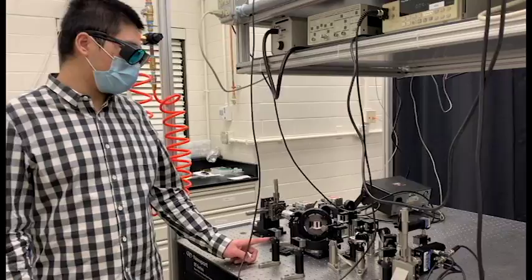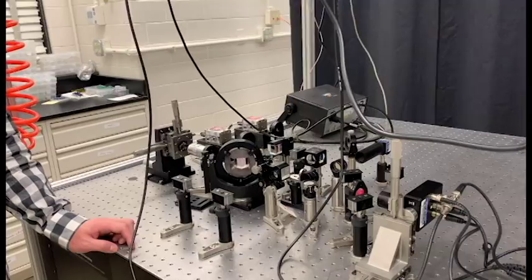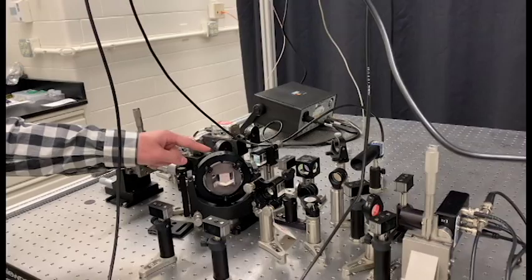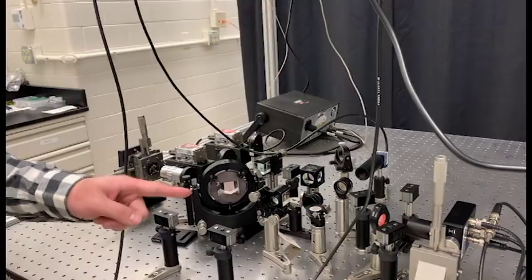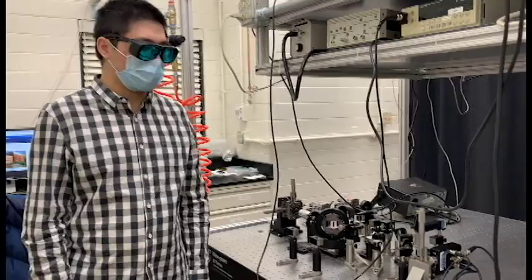This is our newly built pump-probe system called frequency domain probe beam deflection. The difference between this FDPBD system and the TDTR system is that the two beams have a beam offset, which is controlled by this instrument. Instead of measuring the thermal reflectance, we are measuring the beam deflection by this detector. As a result, we can finish the measurement of the thermal diffusivity of transparent samples.